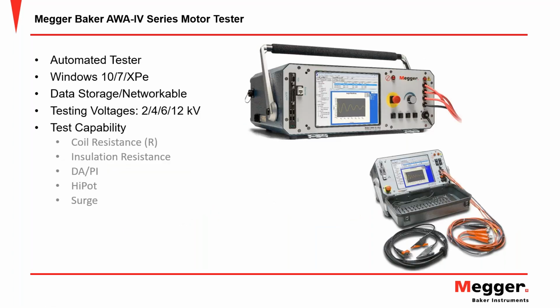So the AWA itself, it is an automatic tester. It comes with, at this point we are producing it with, Windows 10. In the past it's had 7 and XP embedded. It does have data storage and access database. It's networkable. Test voltage is 2, 4, 6, and 12 kV, and has the test capability of the coil resistance, insulation resistance, DAPI, high pot, and surge. So we see here the 2 or 4 kV is this size. We get a bigger size for the 6 and 12 kV testers.